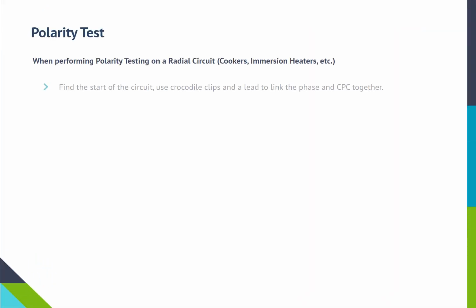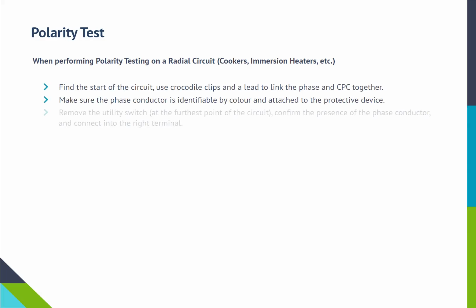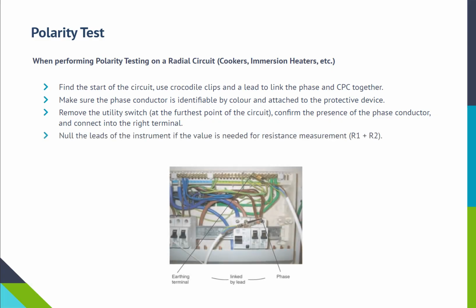When performing polarity testing on a radial circuit, cookers, immersion heaters, etc., find the start of the circuit, use crocodile clips and a lead to link the phase and CPC together. Make sure the phase conductor is identifiable by color and attached to the protective device. Remove the utility switch at the furthest point of the circuit, confirm the presence of the phase conductor, and connect into the right terminal. Null the leads of the instrument if the value is needed for resistance measurement, R1 plus R2.